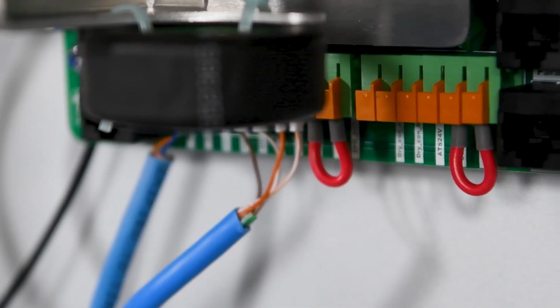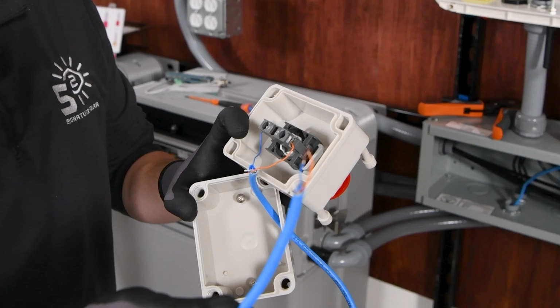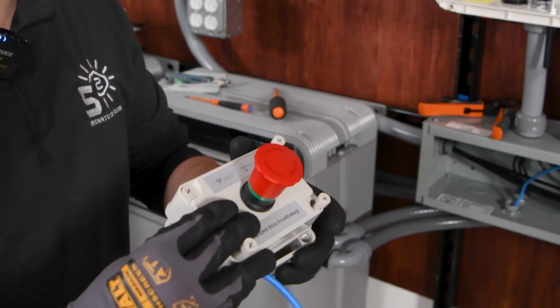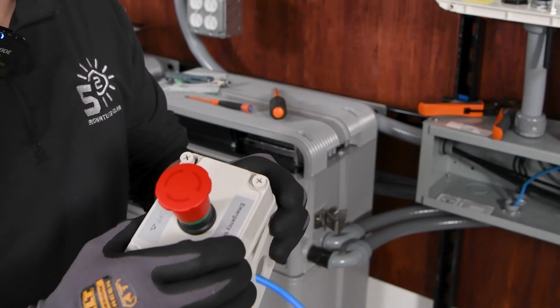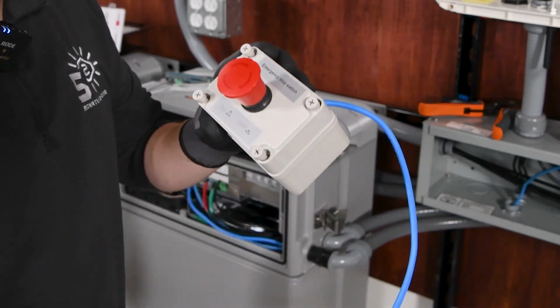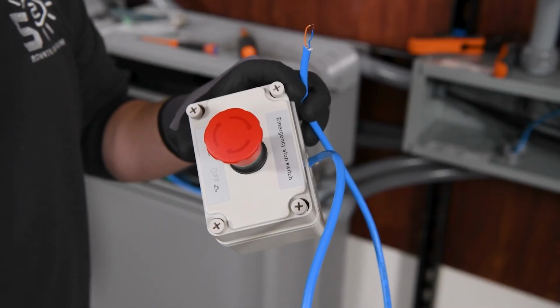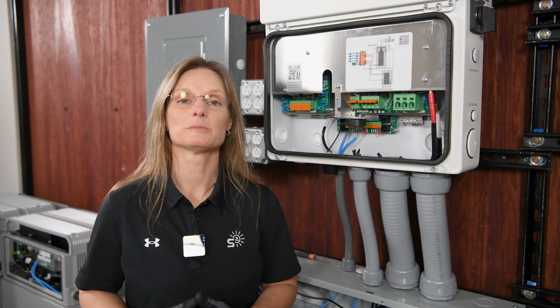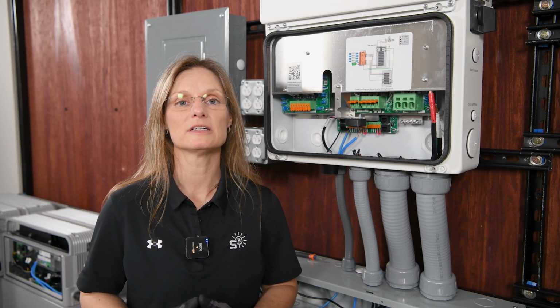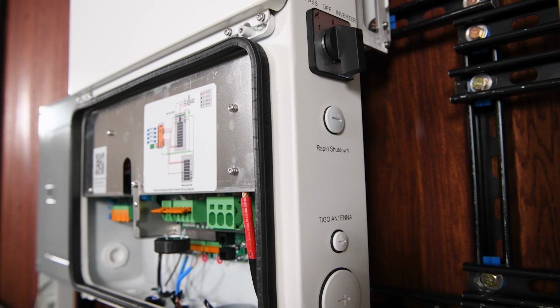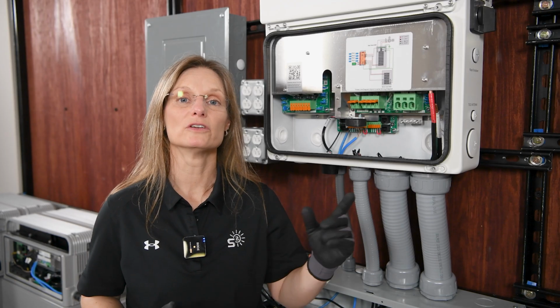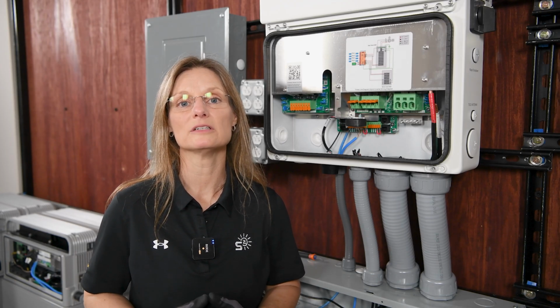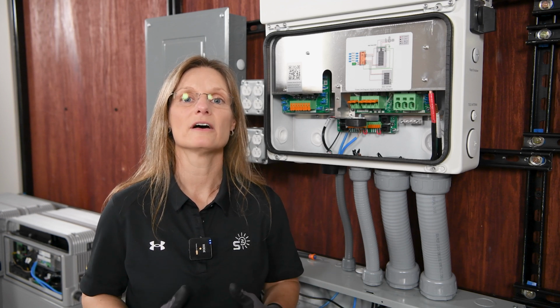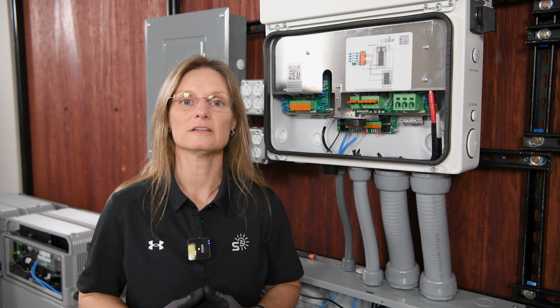Moving across your communications board, you'll notice that there is a rapid shutdown input. This has a red jumper in it, which is a keep alive signal. If you wanted to wire up an external rapid shutdown initiator, you could do that. And when you hit that button for emergency personnel, this would shut off any power from the inverter. Many models that Solis provides comes with a built-in rapid shutdown button, which would be installed here on the side. This being a base model, it does not come with that, but if yours does have a built-in rapid shutdown button on the side, it would shut down all DC voltage coming in from your array.